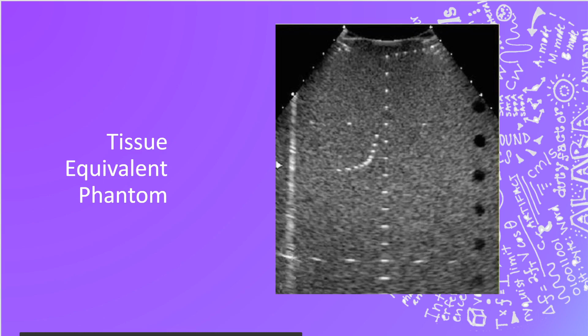Over on the other side here, we're going to have these bars that run through the tissue phantom. Typically, you're going to have a bunch of bars of different sizes. You're going to be told what those sizes are, so 8, 6, 4, 3, and 2 millimeters. So we should be able to measure an 8 millimeter structure here in the near field and an 8 millimeter structure here in the far field. It shouldn't matter where we are in our field. We should get 8 millimeters no matter what. That's testing the accuracy of the machine. Same idea down to the 2 millimeters.